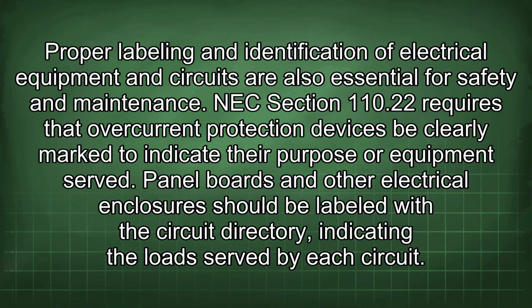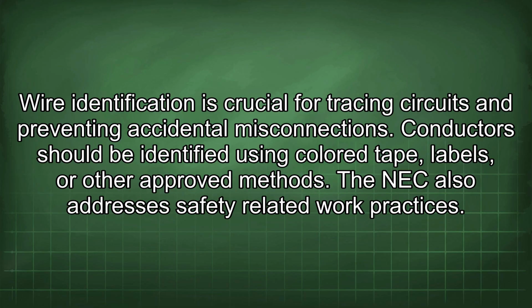Proper labeling and identification of electrical equipment and circuits are also essential for safety and maintenance. NEC Section 110.22 requires that overcurrent protection devices be clearly marked to indicate the purpose or equipment served. Panelboards and other electrical enclosures should be labeled with the circuit directory, indicating the loads served by each circuit. Wire identification is crucial for tracing circuits and preventing accidental misconnections. Conductors should be identified using color tape, labels, or other approved methods.